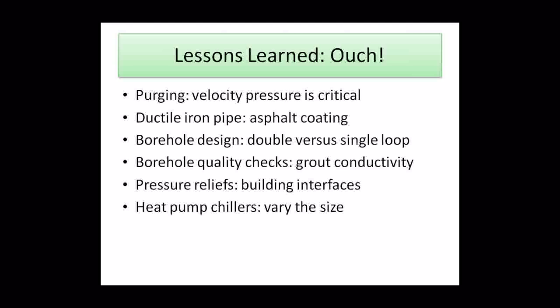We've gone from the double to the single loop arrangement. The reason we did that is the installers, biggest part of our construction cost, $30 million, is the boreholes. We certainly listened to our drillers. They told us it was problematic trying to get 2 loops in 1 hole. We thought it was a great advantage because we get a little bit additional capacity out of 2 loops in the same borehole. We've gone to the single 500-foot deep versus the double 400-foot deep, and the grout is a little bit more stout, 1.2 versus 0.69 on the double design. The grout, we found a place to actually test the conductivity.